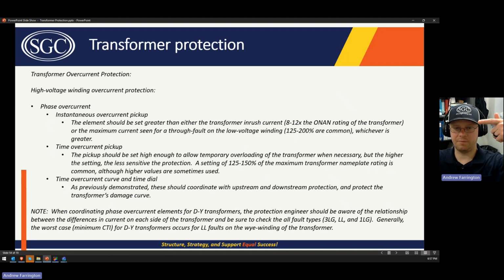So if you have a line-to-line fault, the low side is going to see lower fault current because not all 3 phases are involved. So it's going to be a lower amount of fault current, but then the high side is going to see the same amount of fault current that it would have seen for a 3-phase fault on the low side. Okay, so that has a tendency to crunch those two curves together. Worth noting, a lot of times that gets missed because people look for a 3-line to ground fault, because it's the highest amount of fault current, and it tends to have that current line further down the curve, decreasing the amount of time. But if you do a phase-to-phase fault, it shrinks those curves together. Worth noting.